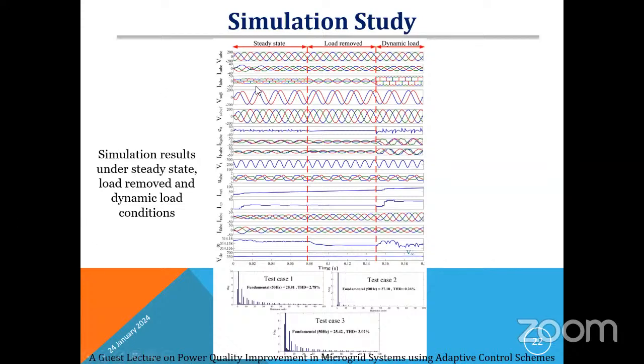currents and load currents. So alpha beta components of the MCCF. Then finally the output voltages of the grid side. This is the grid side. This is the control characteristics of the MCCF. To check the MCCF control performance, we have manually injected the harmonics at the grid side.